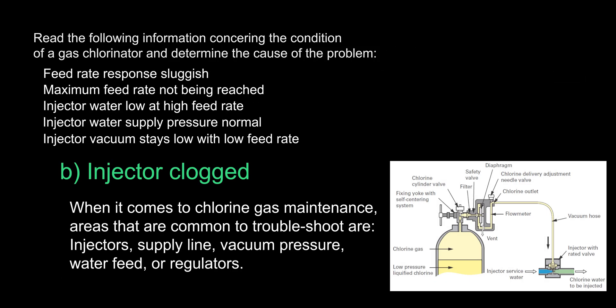The answer is B, injector clogged. The issues described are inherent to that of an injector clog because higher feed rates cannot be achieved even though water pressure is normal and the system works when the feed rate is low. No information is given on whether there is an issue with the supply line, which would be determined with a pressure regulator. Chlorine gas usage is not as common nowadays given the potential for danger associated with it; however, questions about it may still appear on your exams. For more information on chlorine gas maintenance, I have provided two useful links in the description.